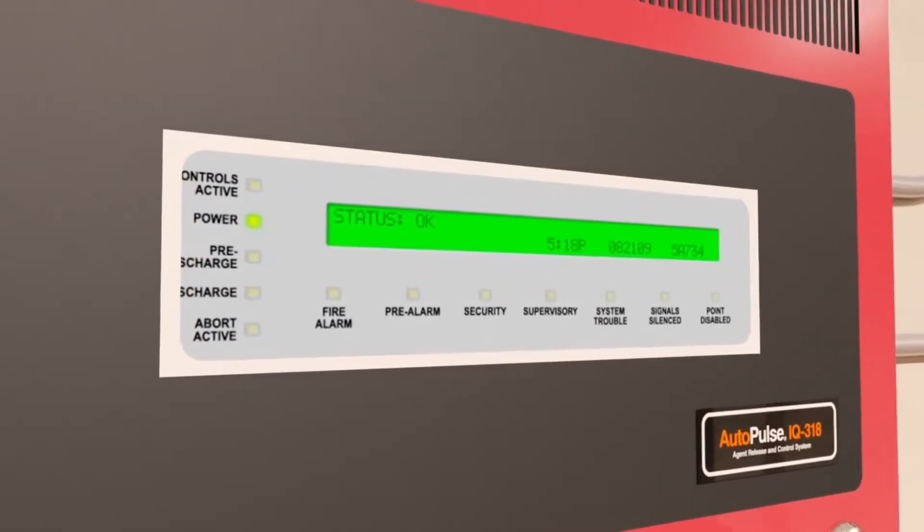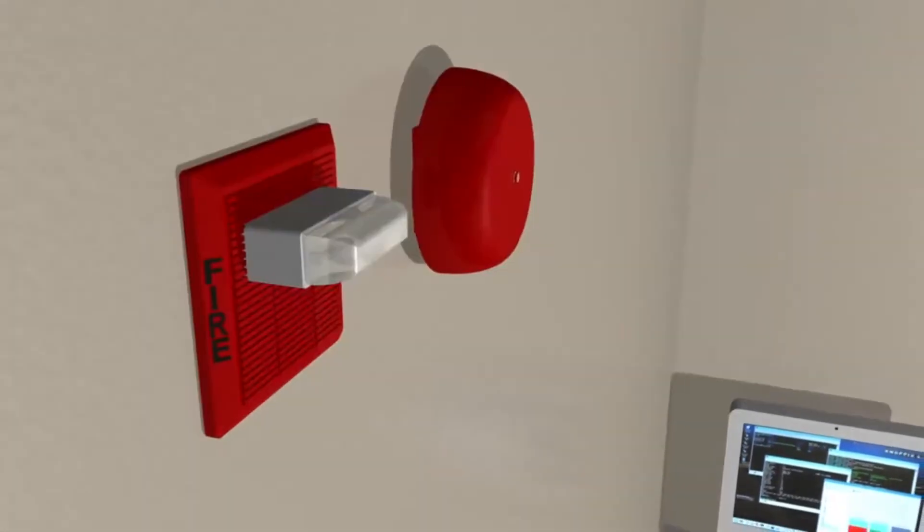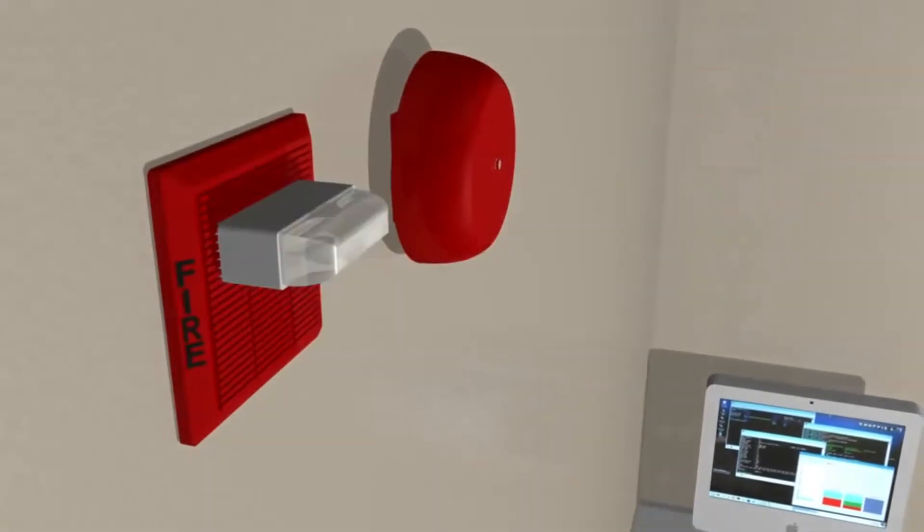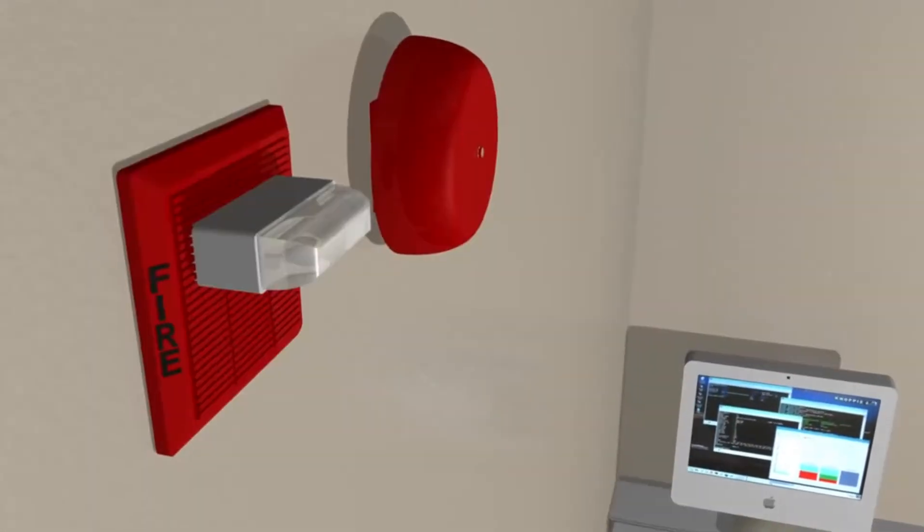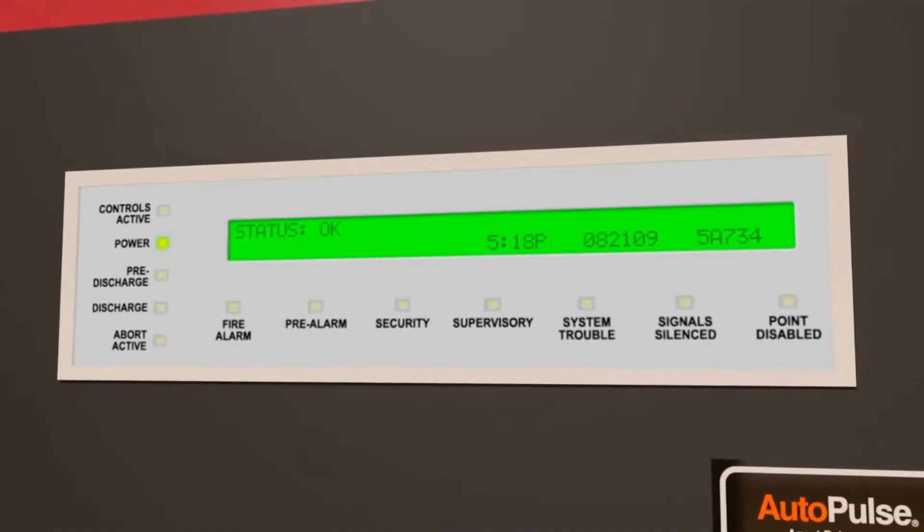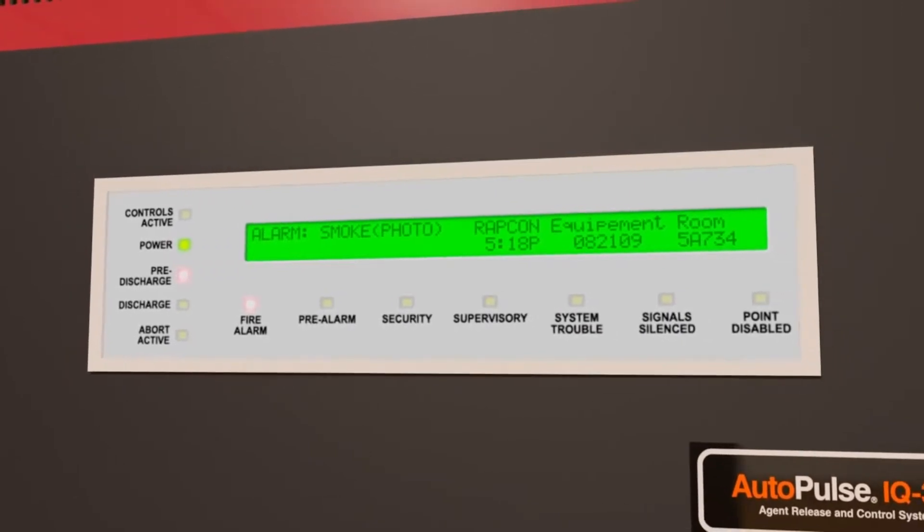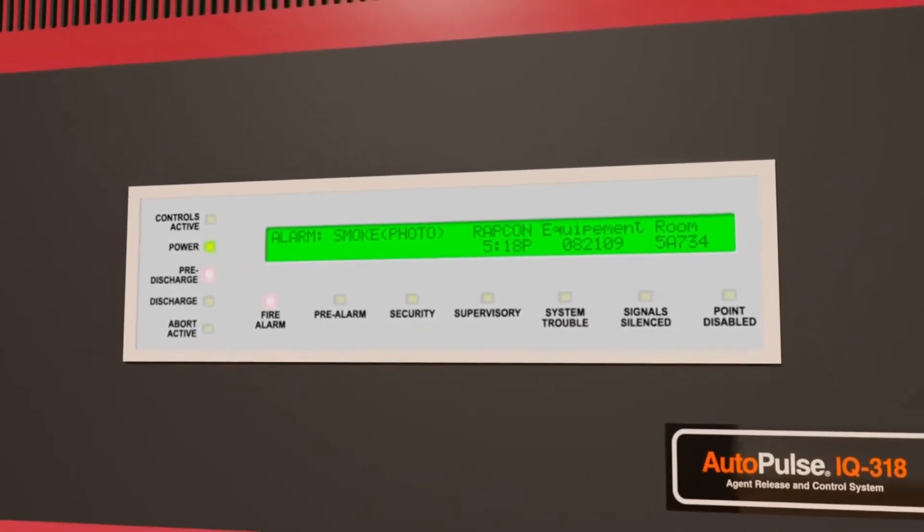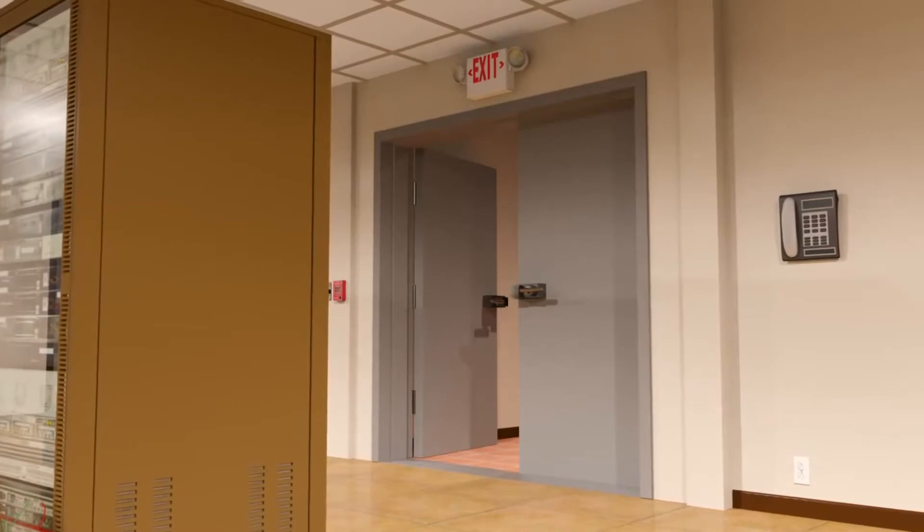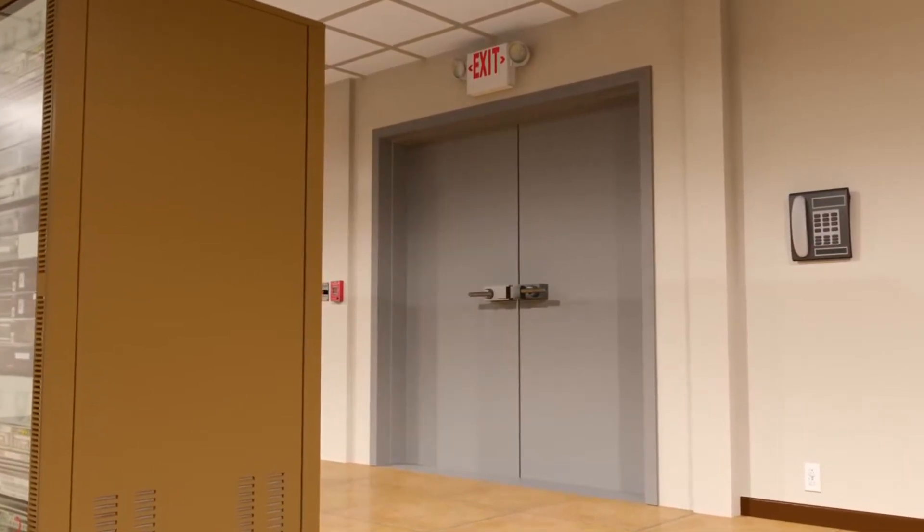Designed to monitor fixed fire hazards, the auto pulse control panel initiates audio and visual alarms throughout the protected area. The auto pulse control panel can also trigger a series of pre-programmed critical actions, like the closing of entryway doors, dampers, or shutting down electrical equipment.